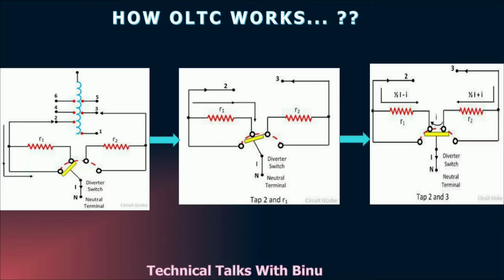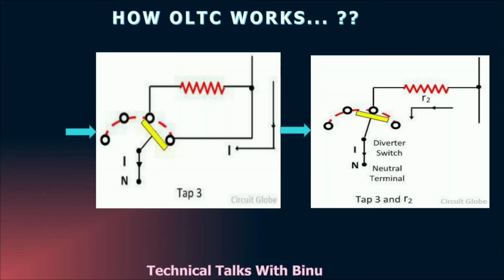An OLTC is working through a make before break principle. Once you are going through this, you will be able to understand how an OLTC is changing the taps without breaking the load. When the diverter switch is switching from tap 1 to tap 2, the connection from the tap 1 is completely broken only once after the connection is completely made in tap number 2. Similarly here also, when the taps are changing from 2 to 3, the connections from the tap number 2 will be completely disconnected only once after the connections are made in tap number 3.